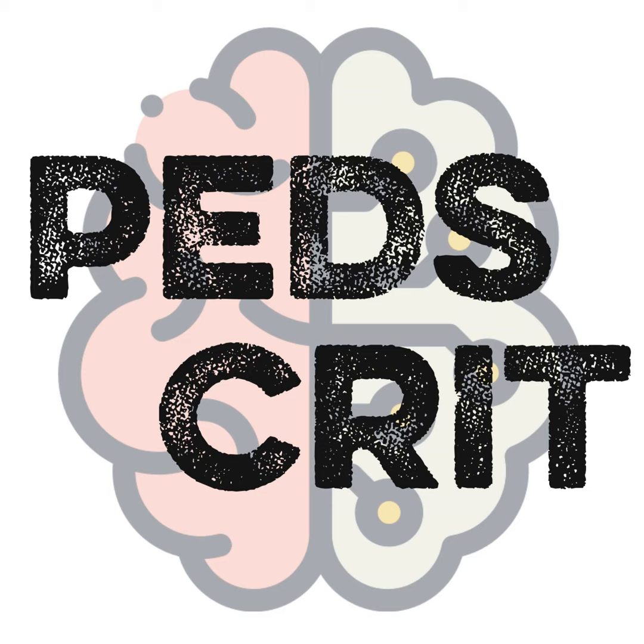So as we think about flow asynchrony, I mentioned it. Once we have triggered and said, okay, it's time, the ventilator's going to give a breath. Once we've triggered that, how does the breath go in? It's how the breath goes in. We have flow pattern, which is: is it a decelerating flow, where it's really fast at the beginning and then slows down, which is the natural way to breathe? Is it a constant flow? We use that a lot more in adults than we do in pediatrics, but we set an exact flow and they get the same flow for the entirety of the breath. Less of a natural way to breathe, but it is the way that traditionally our first ventilators actually gave breaths, with this constant flow across the breath.